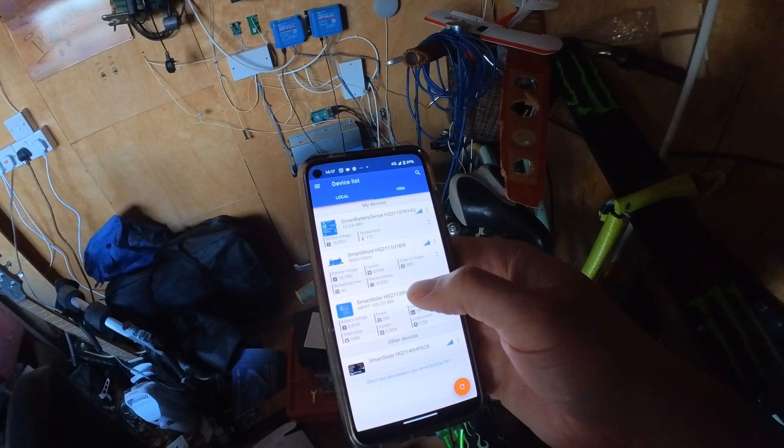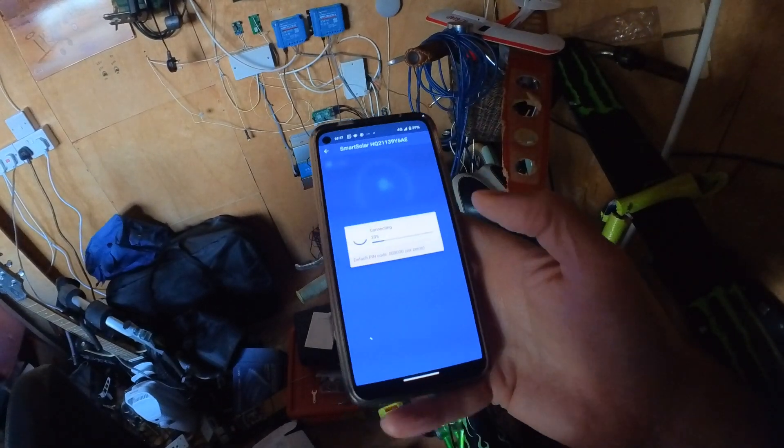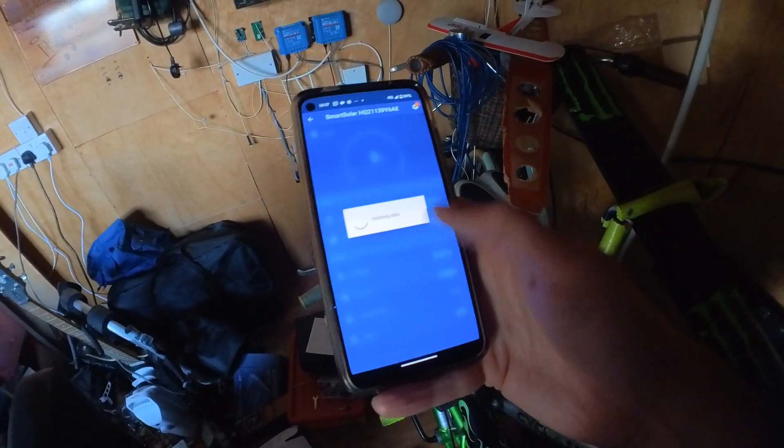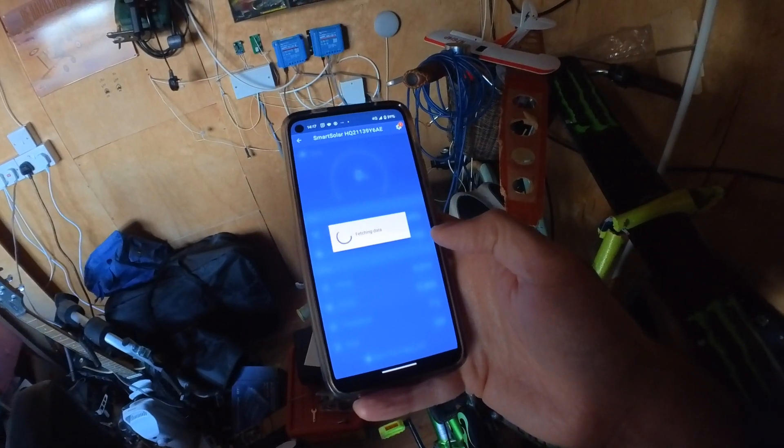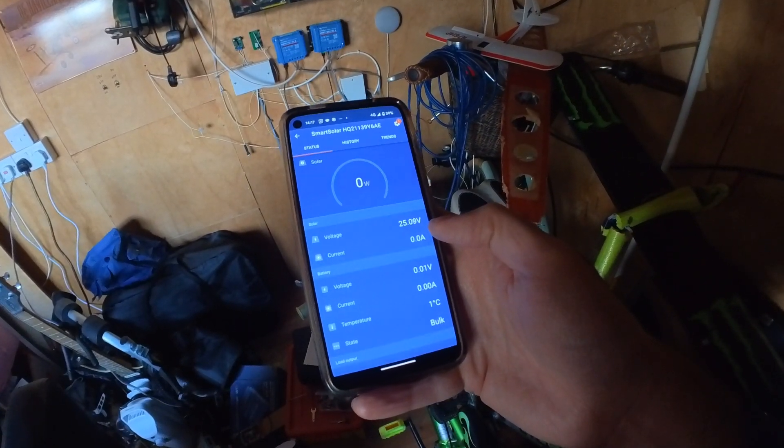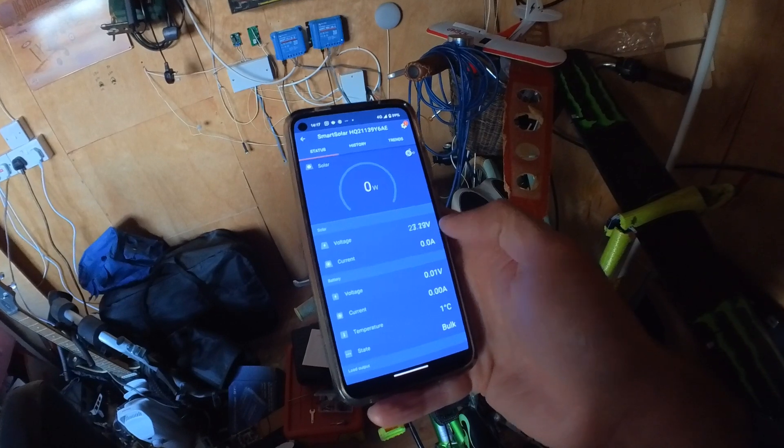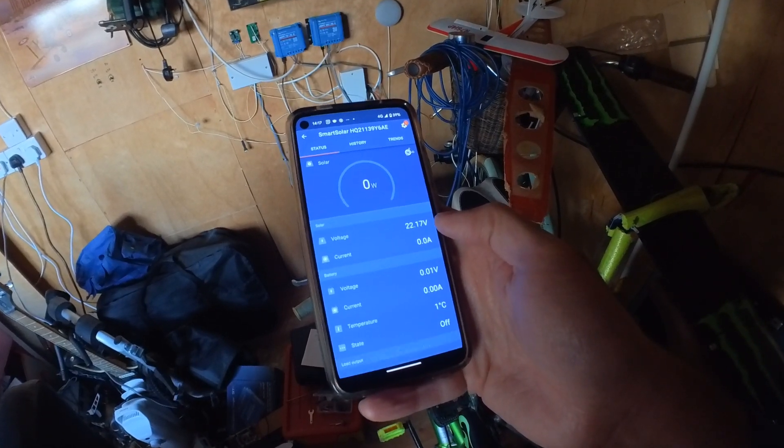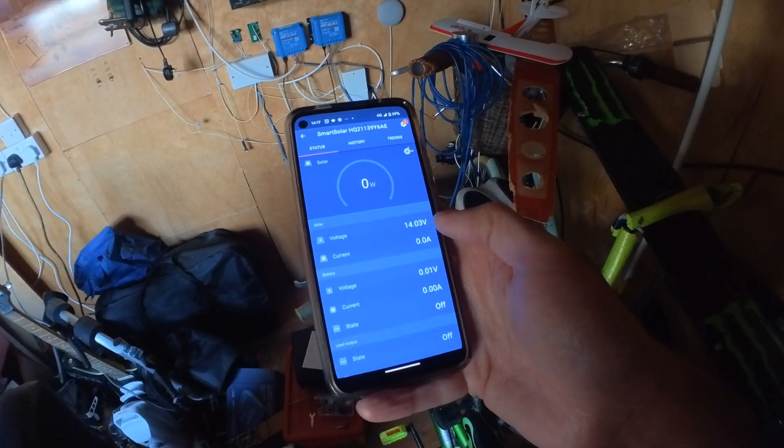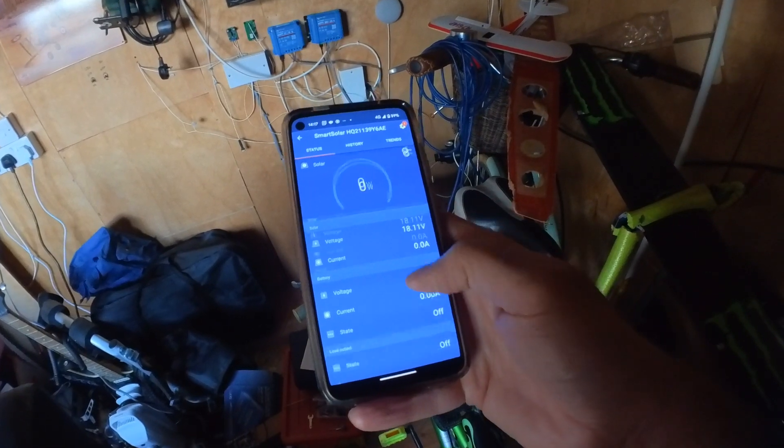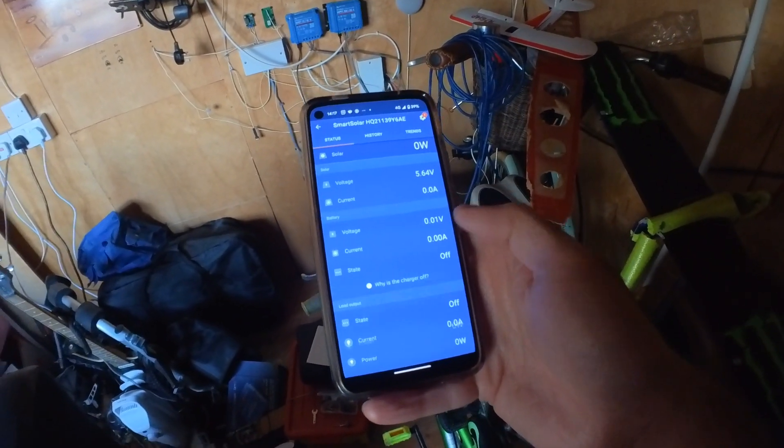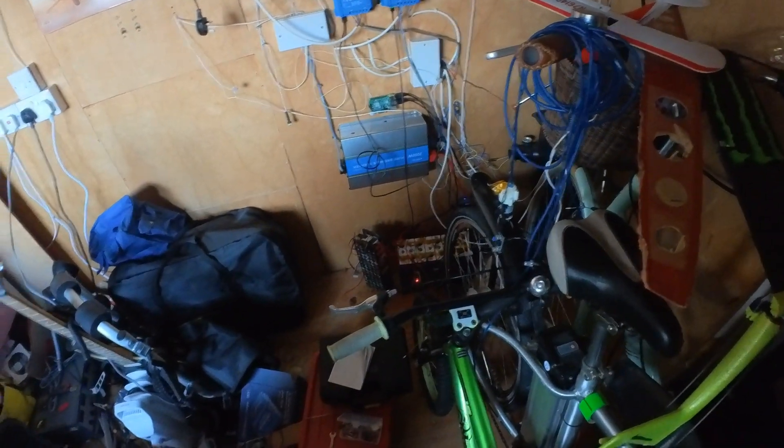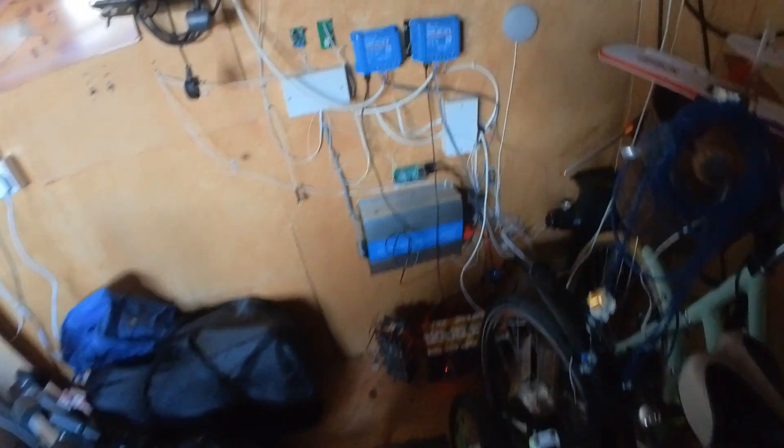If we go to our charge controllers, we can see that they've disconnected because they're on the BMS side. You can see even though we've got some power on the panels, it is all over the place because there's snow on the panels. The battery voltage is 0.01 because the BMS has disconnected, which means everything is disconnected.